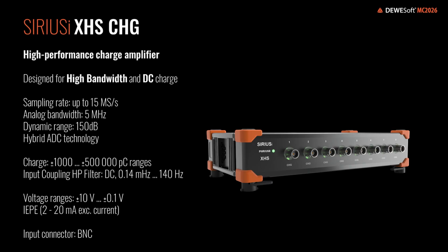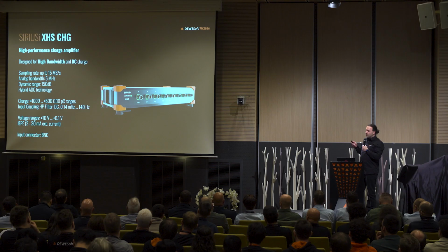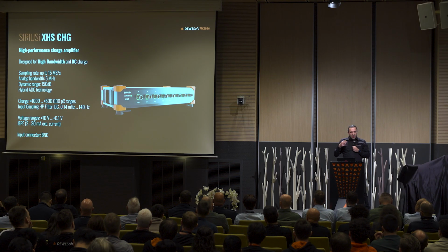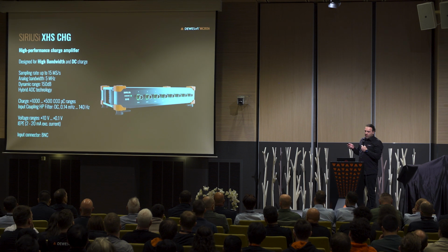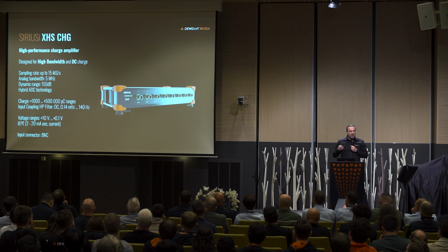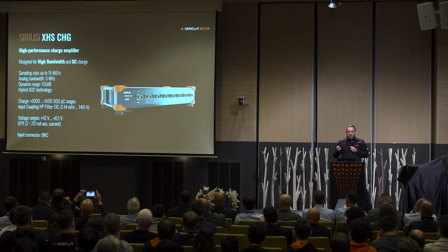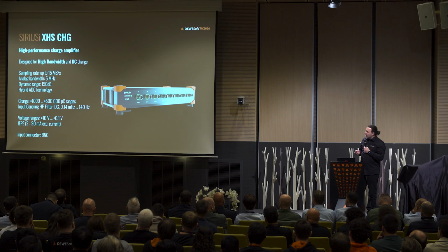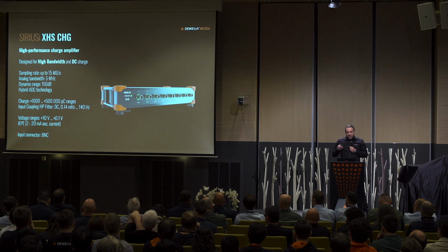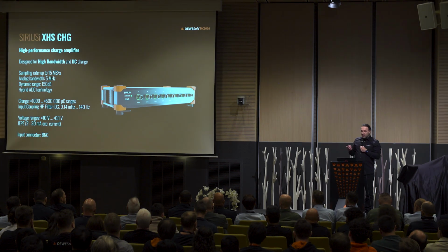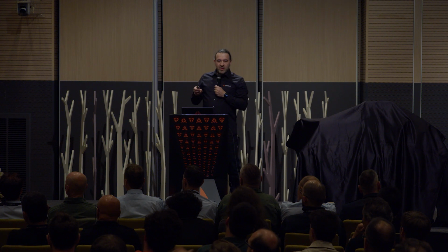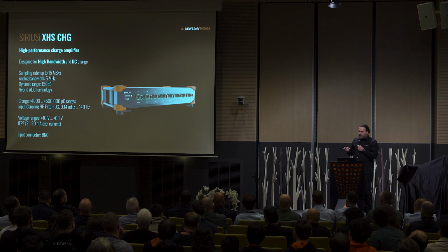We also designed high-speed, high-bandwidth charge amplifier. Here we took XHS amplifier and added DSI charge DC front-end to get the best of both worlds. High-speed performance of XHS and DC performance of DSI adapter. What we achieved is a unique amplifier capable of measuring high-speed events with analog bandwidth of 5 MHz and dynamic range of 150 dB, while also having a DC-like performance with high pass filter with maximum time constant of 1,000 seconds. So this high-pass filter can also be disabled to achieve true DC performance with less than 1 picocoulomb per second drift with no active correction circuitry inside. And yes, you can also connect IEPE accelerometers.